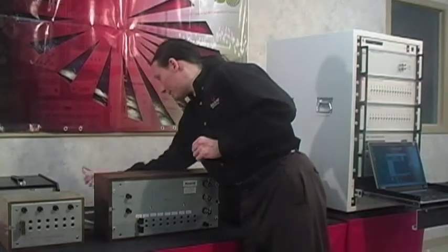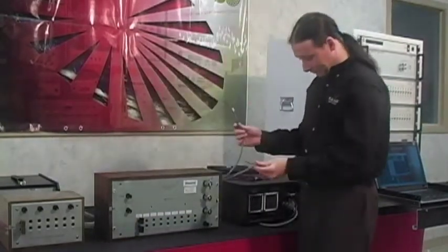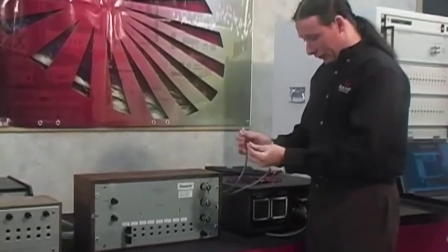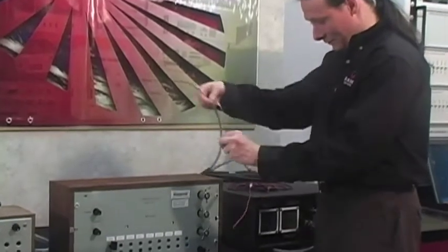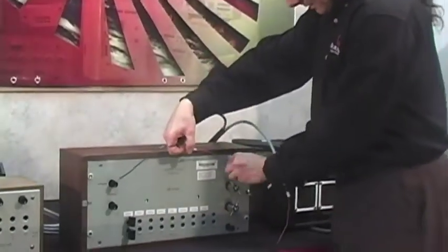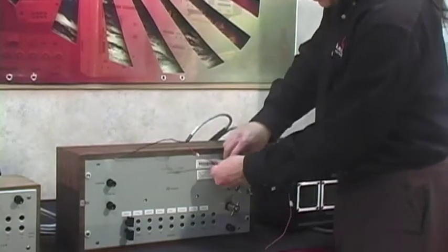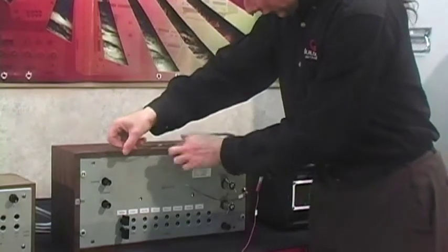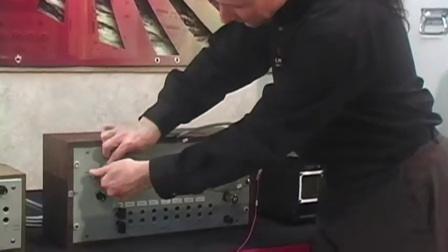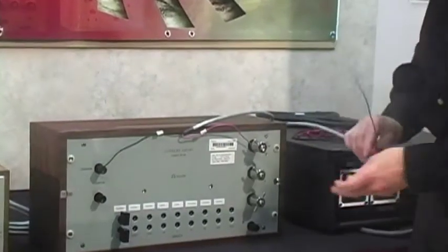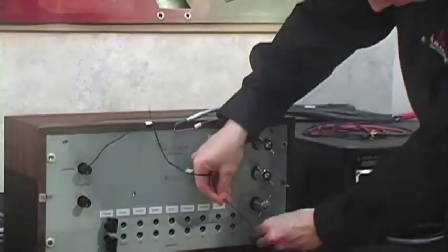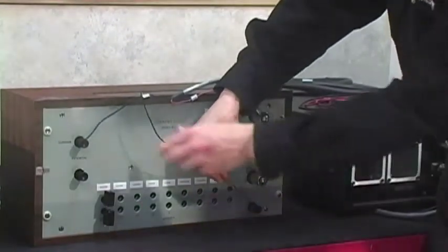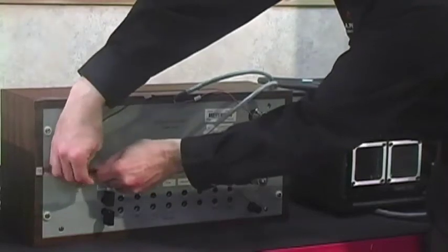So we'll take this channel here, channel 28, and you will want to connect your C1s and your C2s to the input common. So you take your C2, go to the input common up here, and then you'll take your C1, or your P1, P2, and go to the common here. And then to connect for the shunt itself, you'll go down to the lowest range down here, which is your 10 amps max. And this will be your C1, and you'll go to the potential right here.